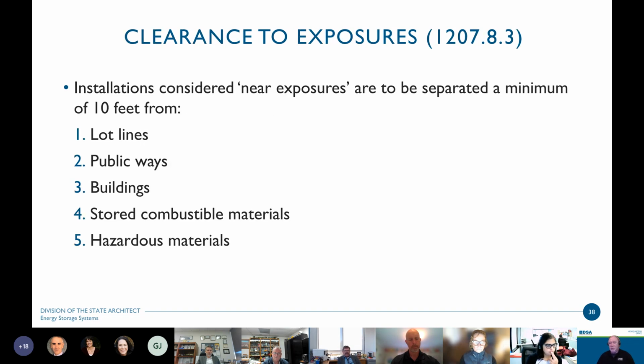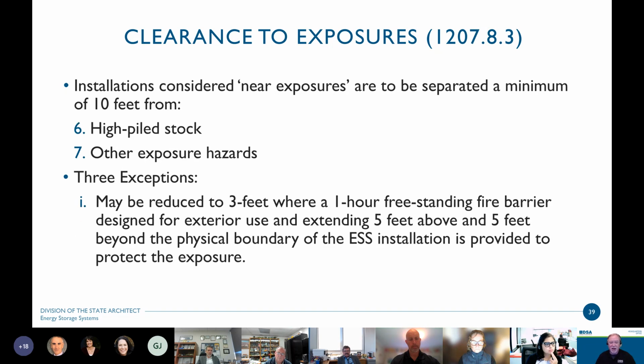So installations considered near exposures are to be separated by a minimum of 10 feet from all these elements here: lot lines, public ways, buildings. You see the shopping list is pretty similar to what we just had for remote, right? But now we can get down to 10 feet. Now there are 3 exceptions which will allow that 10-foot separation distance to be reduced. Exception 1 will permit the reduction down to 3 feet if a 1-hour freestanding fire barrier is constructed. That fire barrier needs to extend at least 5 feet above and 5 feet beyond the physical boundary of the ESS installation. And it's basically there to provide the barrier between the installation and any adjacent exposures.